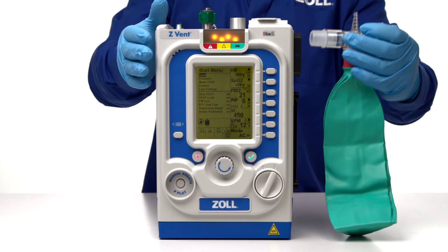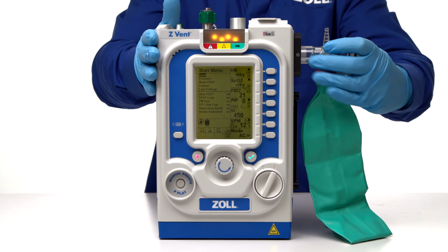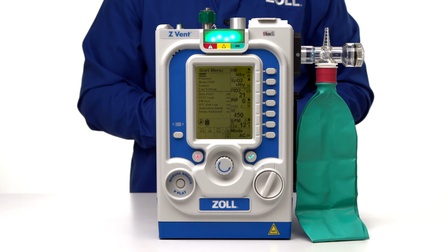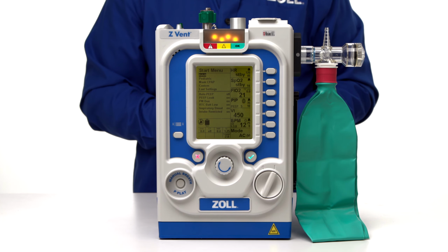ZOLL offers an oxygen reservoir bag assembly kit that allows the use of low-flow oxygen with the ventilator. This provides supplemental oxygen to the patient via a flow meter or oxygen concentrator. Oxygen is delivered through the fresh gas intake port when the internal compressor cycles to deliver a breath.